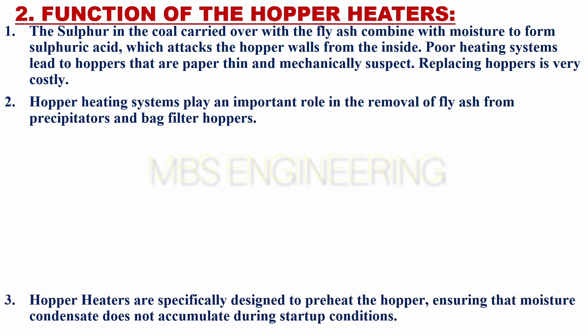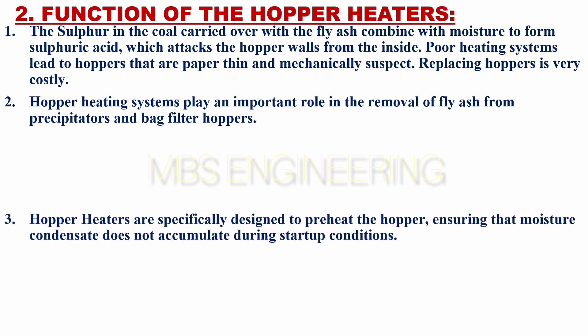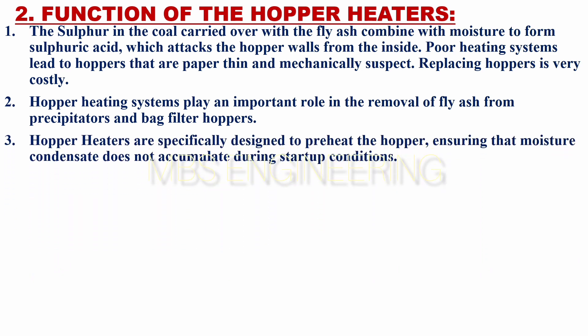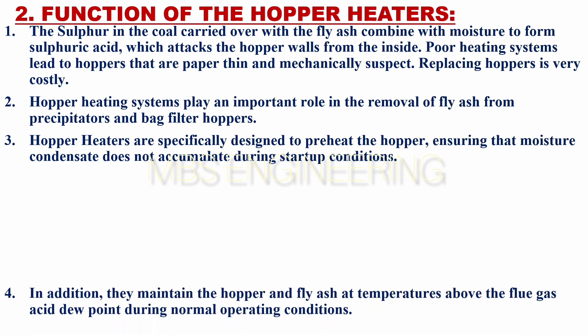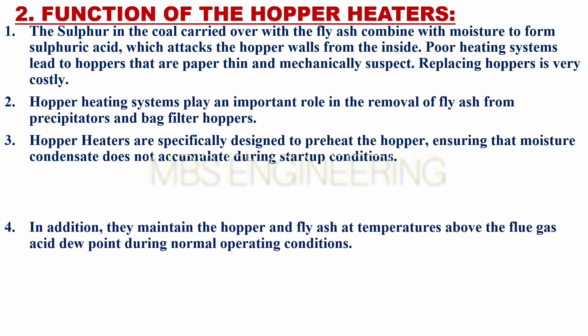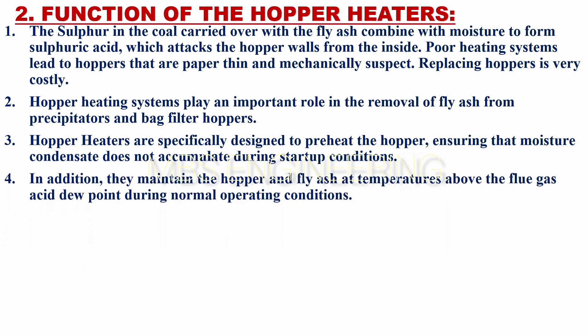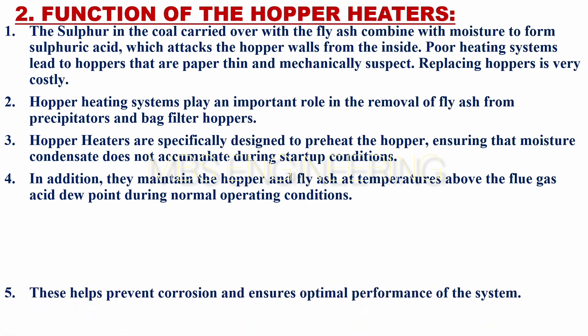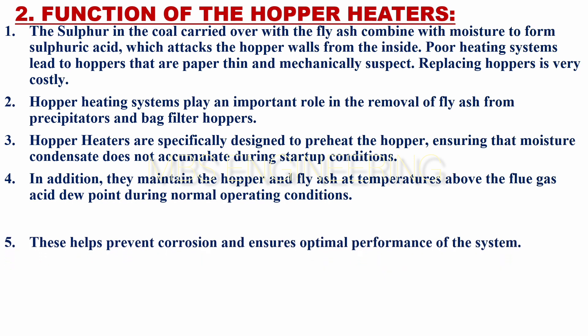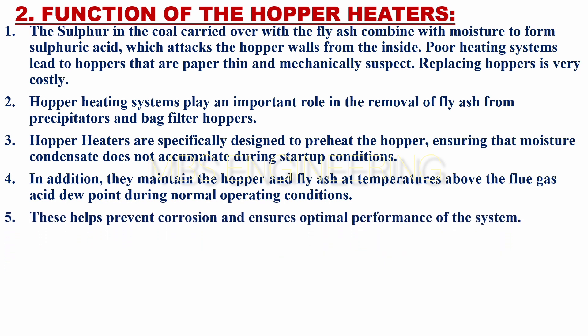Hopper heating systems play an important role in the removal of fly ash from precipitators and bag filter hoppers. Hopper heaters are specifically designed to preheat the hopper, ensuring that moisture condensate does not accumulate during start-up conditions. In addition, they maintain the hopper and fly ash at temperatures above the flue gas acid dew point during normal operating conditions. These help prevent corrosion and ensure optimal performance of the system.